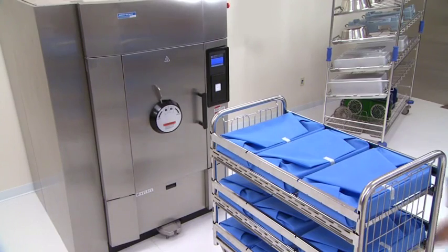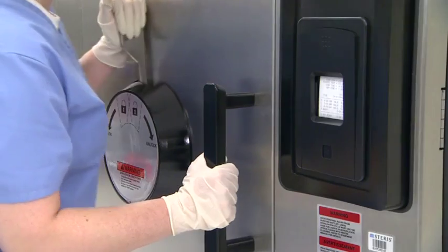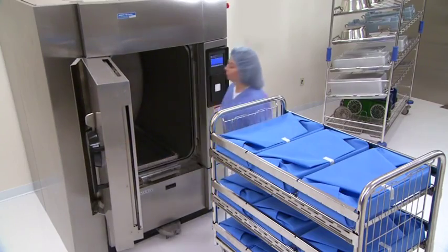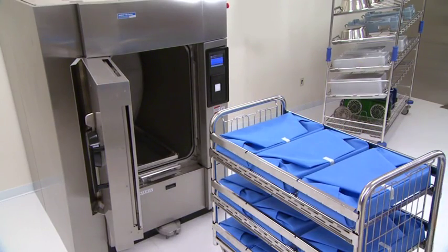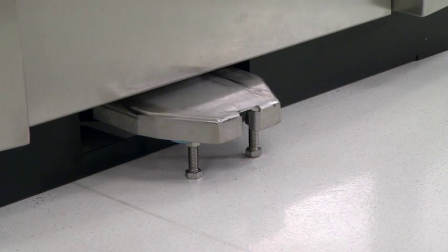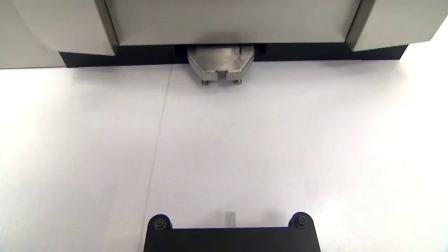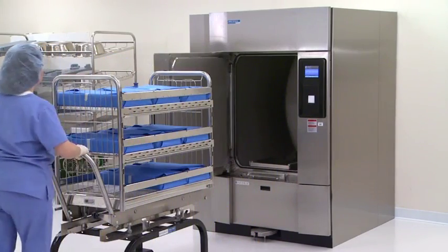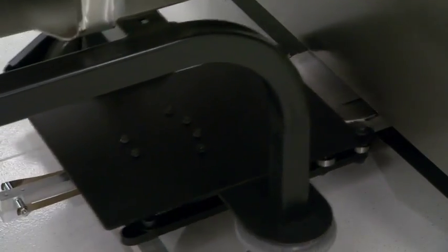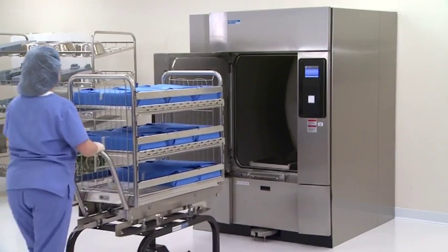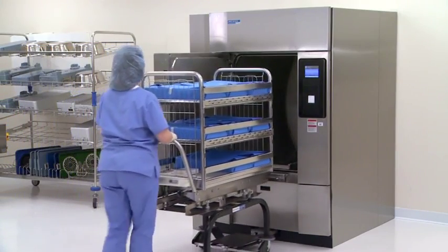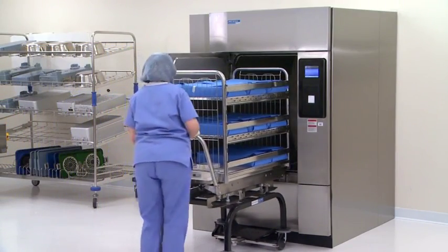Now, let's discuss transferring a carriage. First, open the sterilizer door. Verify the loading car is securely fastened to the transfer carriage. Align the front end of the transfer carriage with the dock at the base of the sterilizer. Roll the carriage forward until the guide assembly aligns with the sterilizer floor dock. If the transfer carriage alignment is off-center during the approach to the sterilizer, the caster lock disengages. Swiveling casters unlock, allowing for easier alignment of the transfer carriage with the sterilizer chamber.